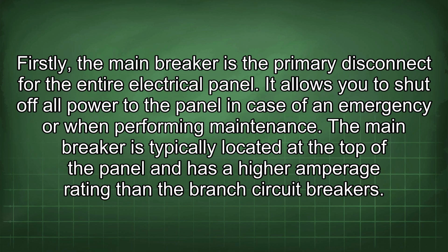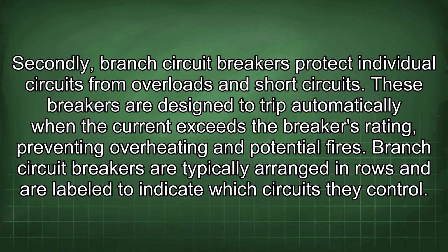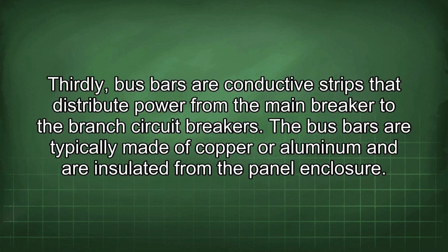The main breaker is typically located at the top of the panel and has a higher amperage rating than the branch circuit breakers. Secondly, branch circuit breakers protect individual circuits from overloads and short circuits. These breakers are designed to trip automatically when the current exceeds the breaker's rating, preventing overheating and potential fires. Branch circuit breakers are typically arranged in rows and are labeled to indicate which circuits they control. Thirdly, bus bars are conductive strips that distribute power from the main breaker to the branch circuit breakers. Bus bars are typically made of copper or aluminum and are insulated from the panel enclosure.